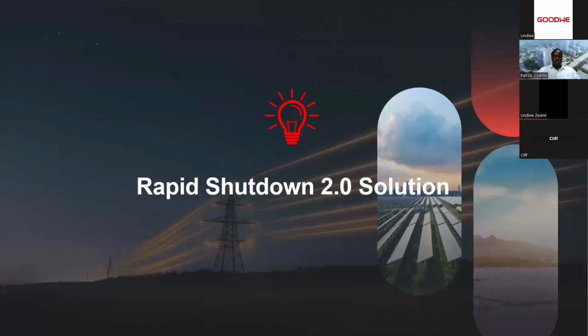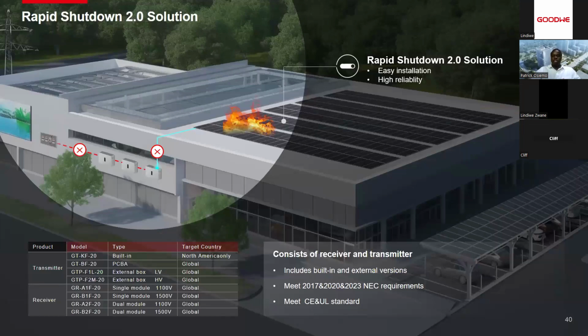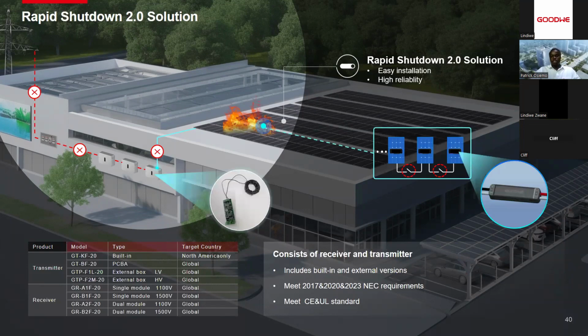Now with the rapid shutdown 2.0, the inverter is able to incorporate rapid shutdown devices on your PV strings. This is quite important in case of fire outbreaks on the roof, or even within the company, with respect to the PV strings. With the rapid shutdown devices, the inverters are able to stop generation and disconnect the power from the particular affected PV strings. You can also get alerts on your inverter to inform you of the hazard. So it is easy to install and highly reliable for highly sensitive systems.